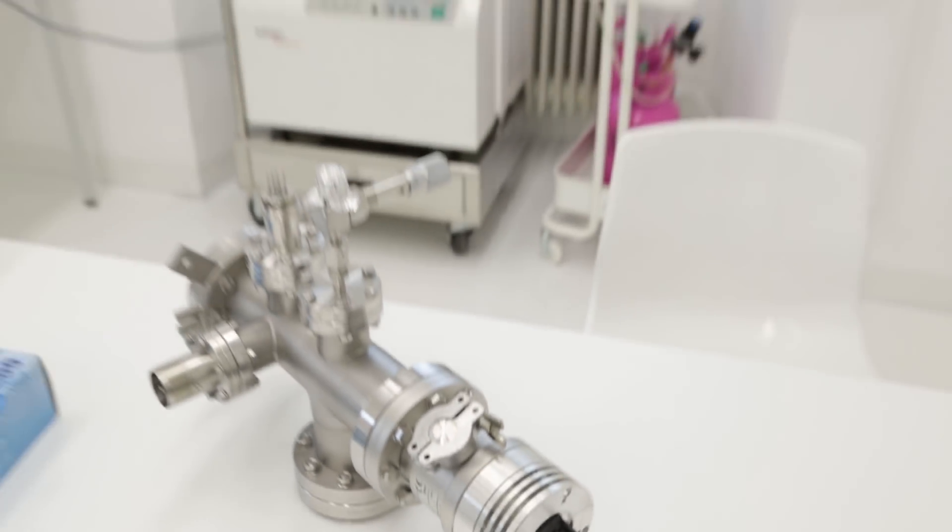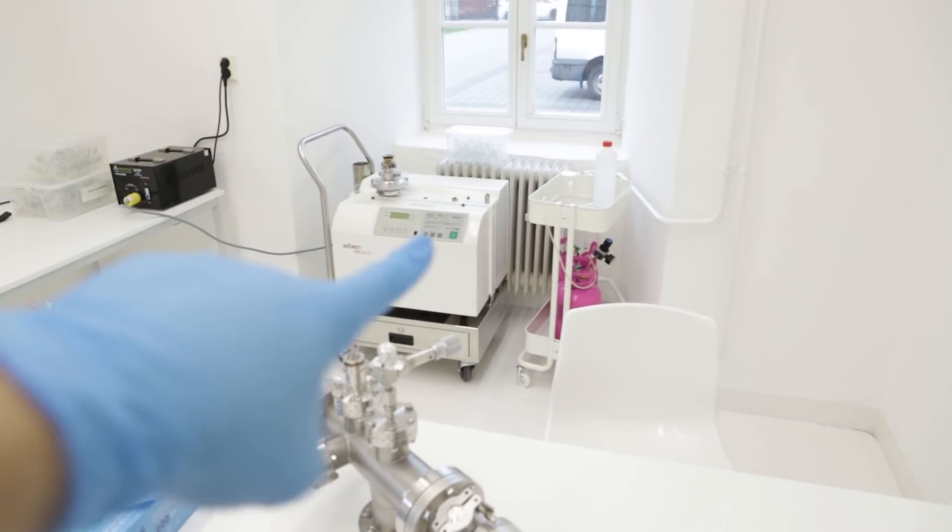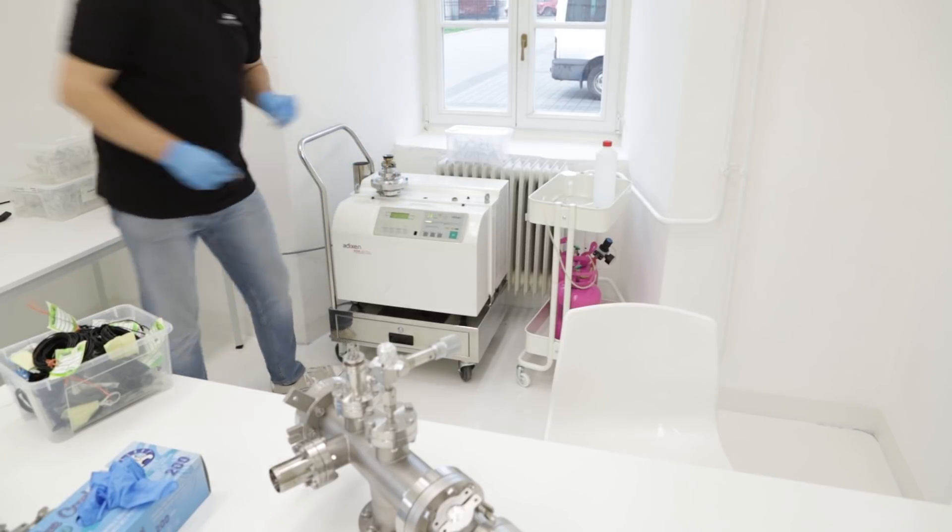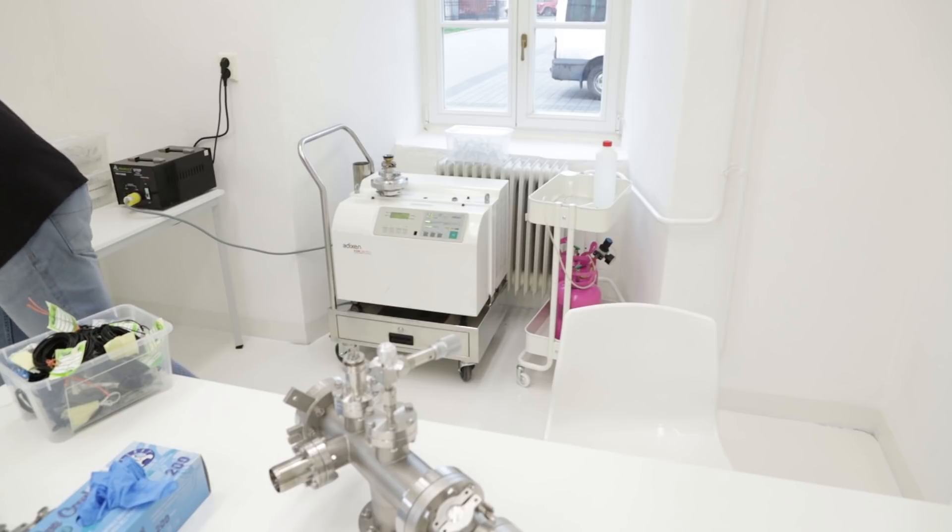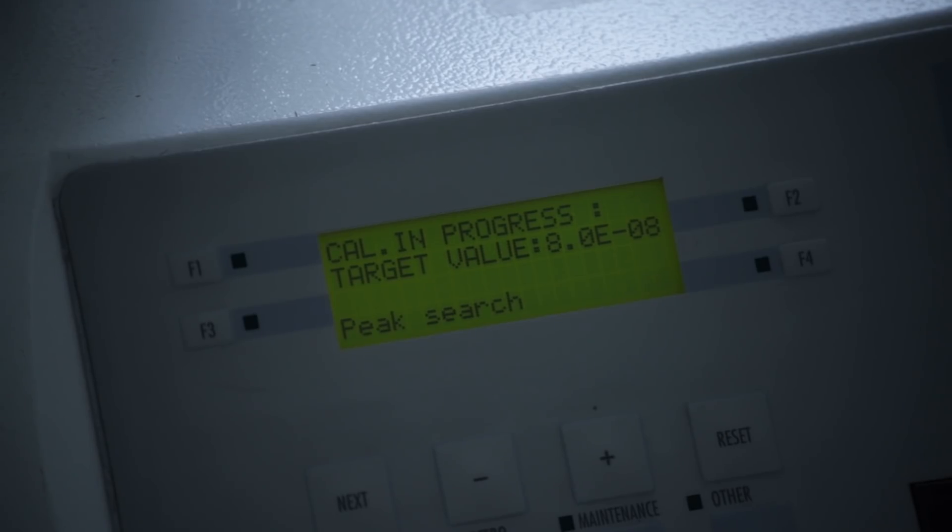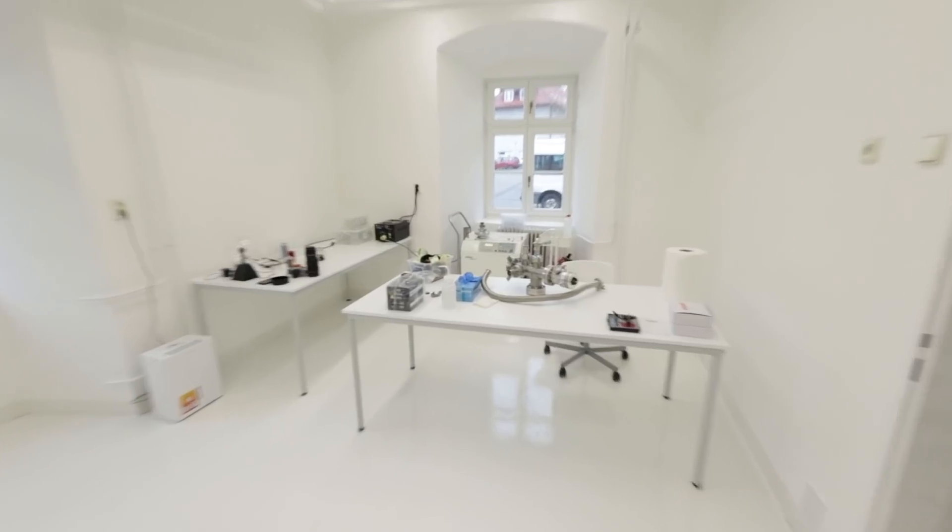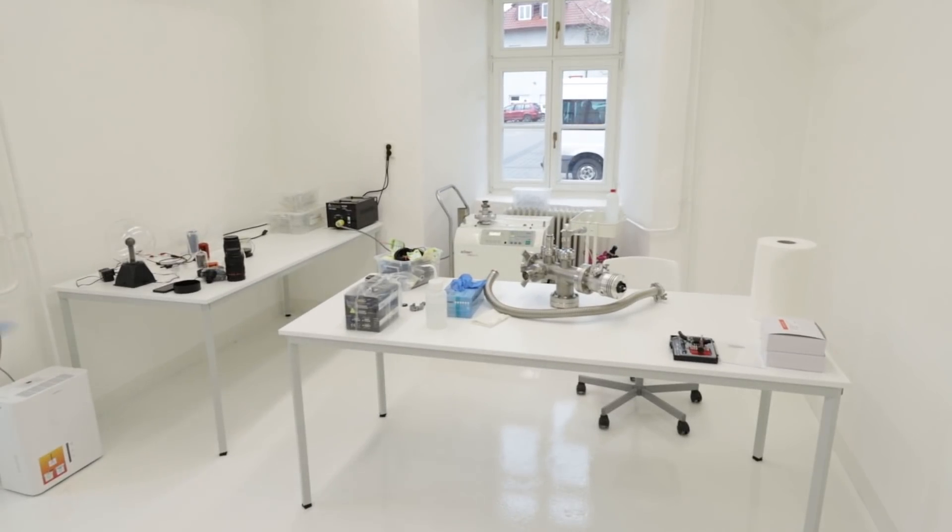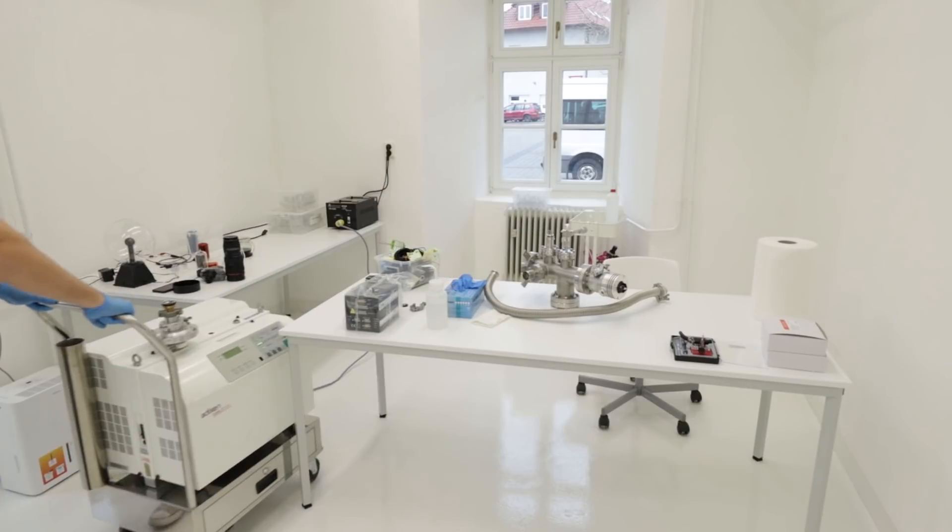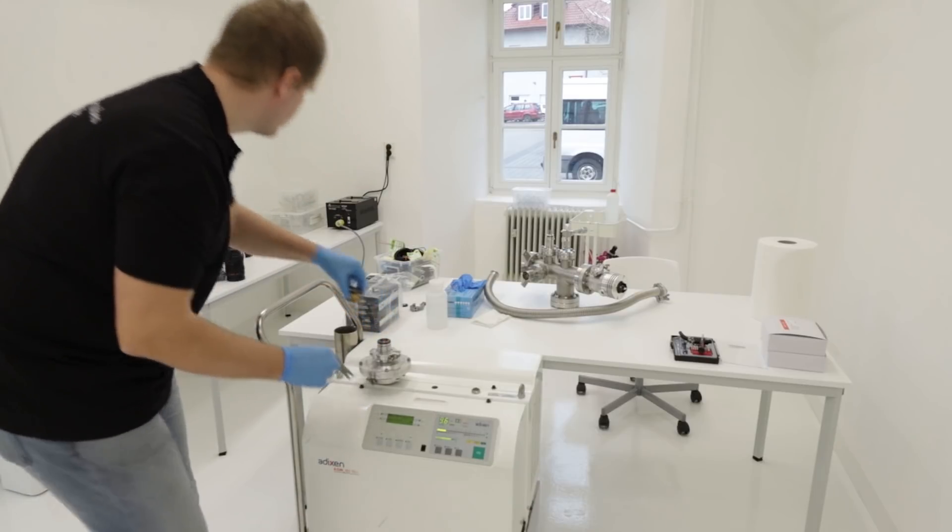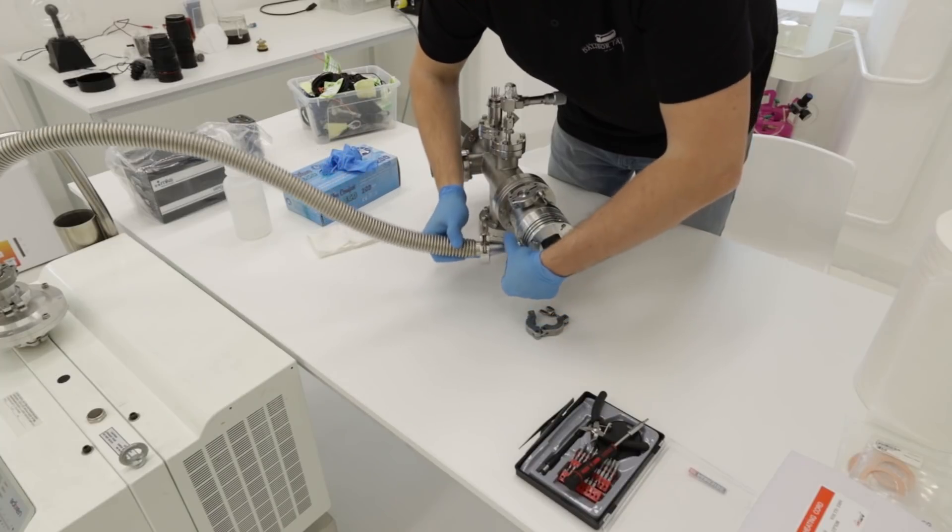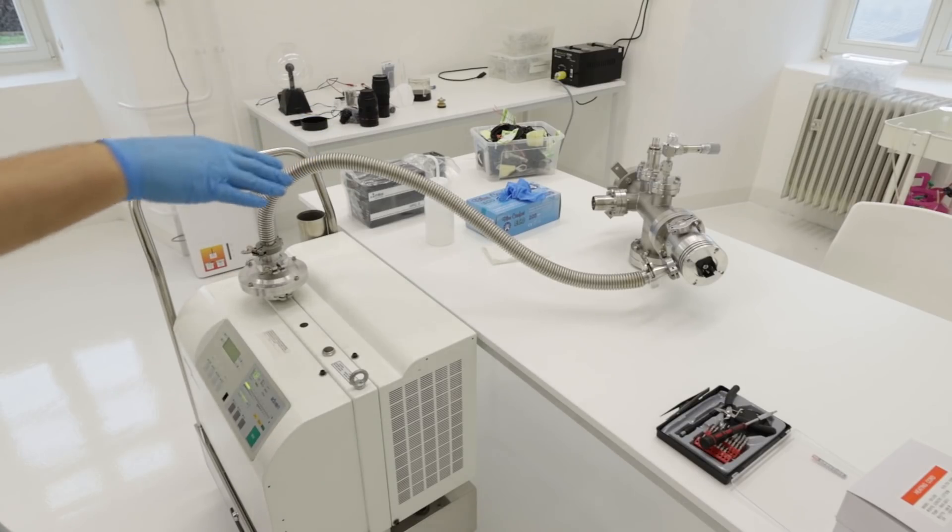Now it's time to check it for leaks with the leak detector which is the machine over here. It needs some time to get calibrated before we can hook it up to the chamber. So it's ready for leak checking.